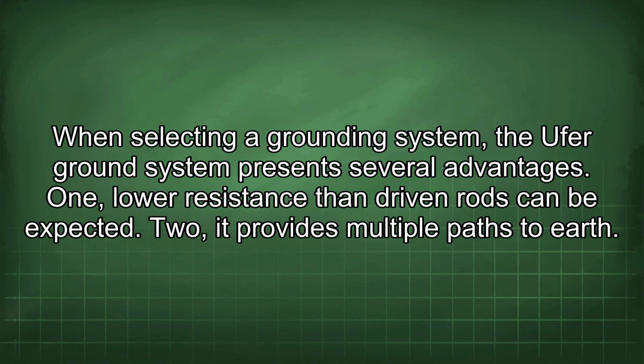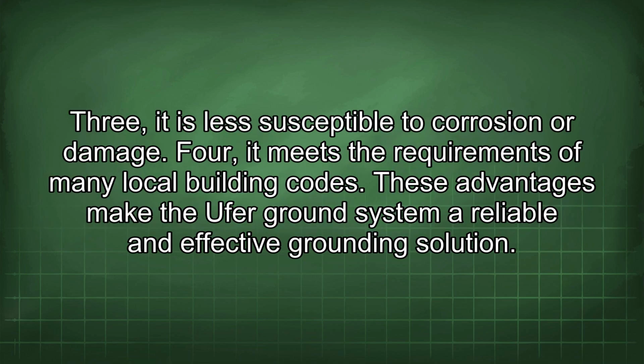When selecting a grounding system, the Ufer ground system presents several advantages. 1. Lower resistance than driven rods can be expected. 2. It provides multiple paths to earth. 3. It is less susceptible to corrosion or damage. 4. It meets the requirements of many local building codes. These advantages make the Ufer ground system a reliable and effective grounding solution.